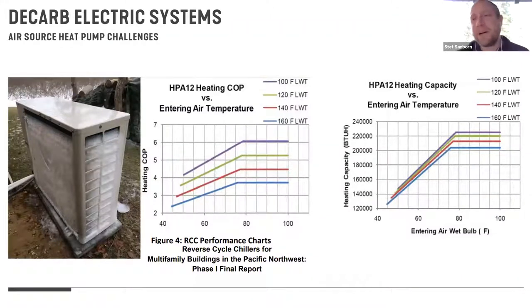As you guys probably well know, if you're sizing heat pump systems in cold climates, there are two things that are going to drastically impact both your selection and your performance. Most air source heat pumps that are trying to produce heat, and that's where we typically run into challenges. We have heat pumps and heat chillers plus cooling towers that work really well in the summer. That technology is known. It's this wintertime performance in cold climates that's especially challenging.